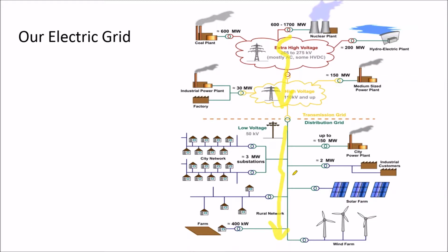And that actually sets how large of a solar farm you can interconnect. Interconnecting to a distribution circuit, there's a couple of things at play here. The first is, what's the physical capacity of that line? If it's a 50 kilovolt distribution circuit, typically you look at how large of an electric service you can get from the power company. If I'm an industrial customer, I might get a 4 megawatt power service, and I could in turn supply about a 4 megawatt solar power plant on one commercial transformer that's connected to your distribution lines.